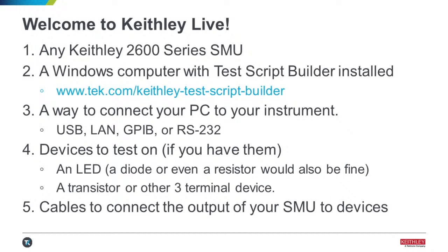Oh, and of course, you'll need Test Script Builder installed. That's what I'm going to be using today. To write in TSP or program your instrument, you don't really need Test Script Builder. It's just a helpful tool. It's an integrated development environment, an IDE built around TSP. So it makes it a little bit easier to send commands to the instrument and code and save scripts onto the instrument, and we'll go through all those different aspects of it.